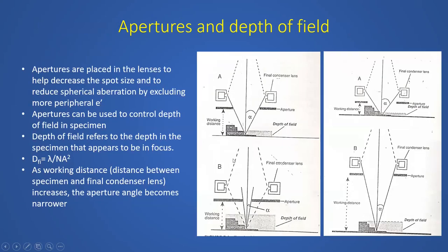Okay, the other important thing is apertures. We have apertures for both TEMs and SEMs. You have lots of apertures, condenser lens apertures, and for TEM you have objective apertures. So apertures play a very important role in SEM as well. Apertures are placed inside the lenses and help to decrease the spot size and to reduce the spherical aberration by excluding the peripheral electrons. They can also be used to control the depth of field in the specimen.